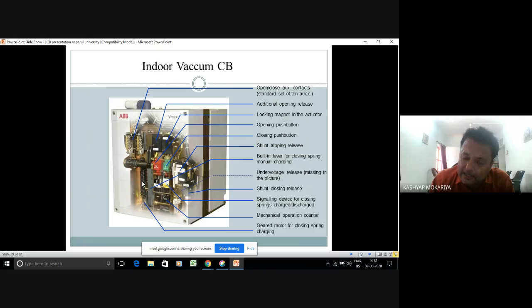Once the breaker is dispatched from the industry, it comes to your industry. Suppose it enters at the gate, then the particular department person will be called. It will not be immediately on the site. Any type of device in electrical engineering, whether it is a breaker, a battery, or a motor, is first put in the storage yard. In the storage yard, sufficient cooling arrangements and sufficient cleanliness are there, and then, at the date of commissioning, the breaker is put on site.